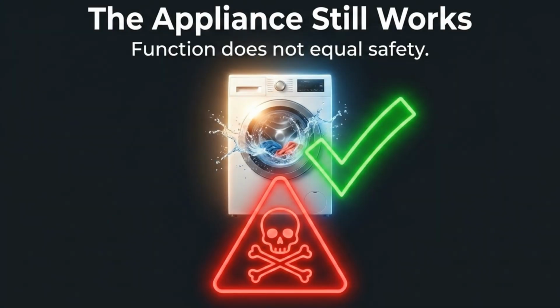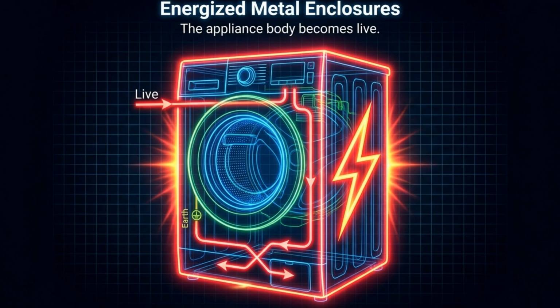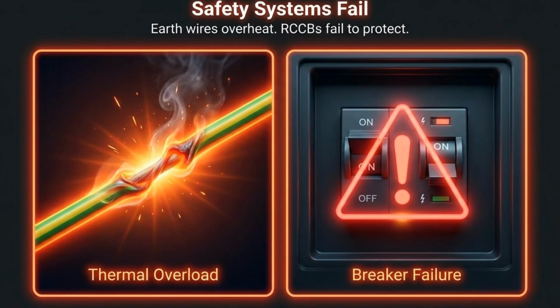It is crucial to remember that just because an appliance continues to function, it does not mean the electrical system is safe. When these wires are reversed, the metal enclosure of an appliance can become live, posing a significant risk of electric shock. This fault causes safety systems to fail, leading to overheating of earth wires and preventing circuit breakers from protecting you properly.